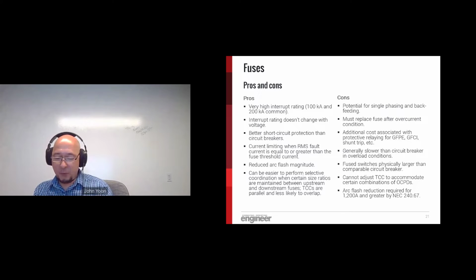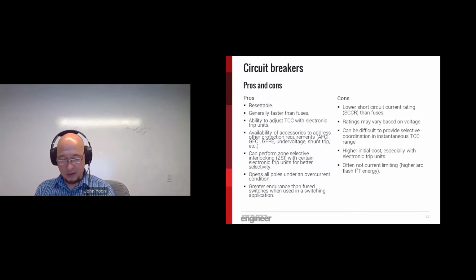But before we leave this, let's just say that most fuses are current limiting, but there is a concept called threshold current ratio. Basically, if the fault current is equal to or greater than the threshold current, the fuse is current limiting, and this ratio can be anywhere from 30 to 65 times the rated ampacity of the fuse. So this is great when you have a high level of available fault current, but for low magnitudes of fault current, like an arc fault event, they may not be particularly effective at limiting that fault current. So we also have pros and cons for circuit breakers. Again, we're not going to read through all of these, but you can see that one of the primary advantages is that we can have solid state trip units that perform additional functions that a fuse can't. We can shape our time current curve so it reacts differently.